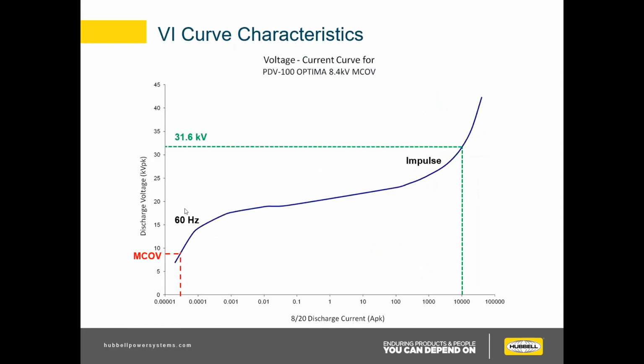So here's what that change in resistance looks like. This is, again, something we can spend a lot of time talking on, but we'll just hit the high points. So for the same 8.4 kV PDV100, which is our heavy duty distribution arrestor, at 8.4 here, it says 0.00005 amps. So, almost nothing, that's what it conducts, all the time, day in, day out. And so this is where the arrestor will last forever.